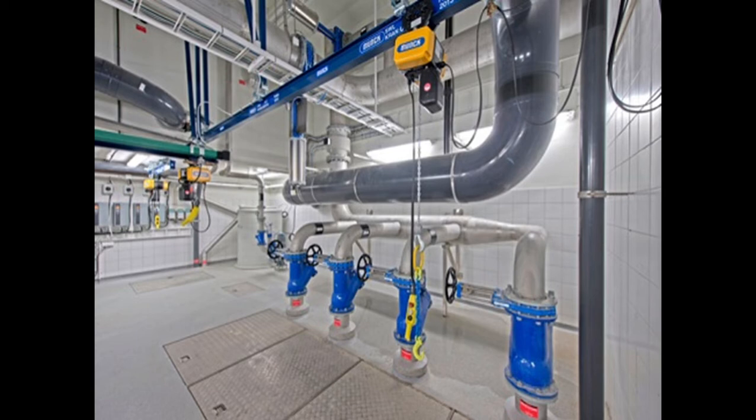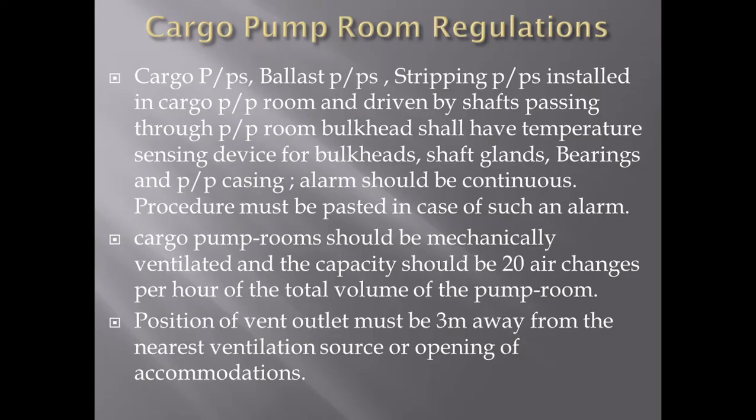Cargo pumps, ballast pumps, and stripping pumps installed in the cargo pump room are driven by a shaft. The alternate drive medium cannot be in the pump room, so it has to be outside — the shaft passes through the bulkhead. In such a case, we need to have temperature sensing devices for bulkhead shaft gland bearings and pump casing. These temperature sensing devices alarm should be continuous, and the procedure for high temperature or emergency must be pasted in the area.